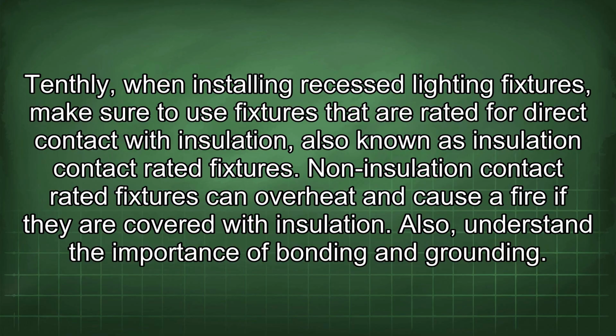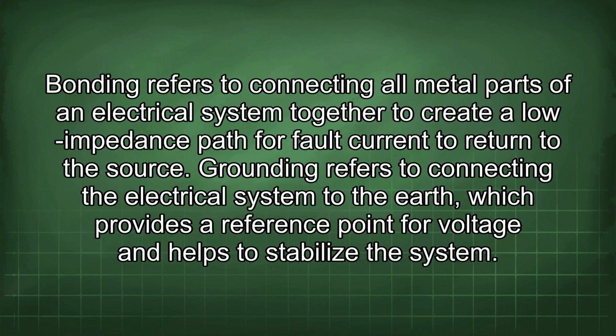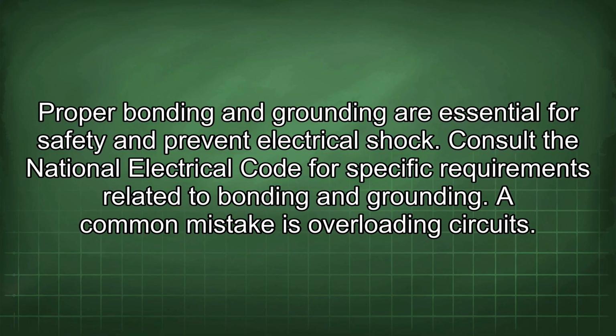Also, understand the importance of bonding and grounding. Bonding refers to connecting all metal parts of an electrical system together to create a low impedance path for fault current to return to the source. Grounding refers to connecting the electrical system to the earth, which provides a reference point for voltage and helps to stabilize the system. Proper bonding and grounding are essential for safety and prevent electrical shock. Consult the National Electrical Code for specific requirements related to bonding and grounding.